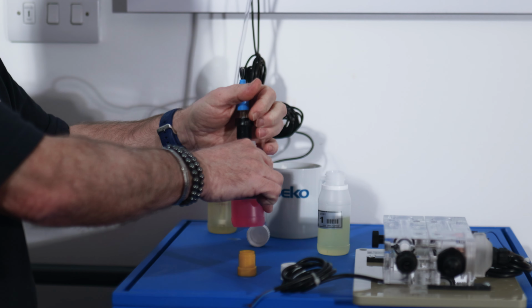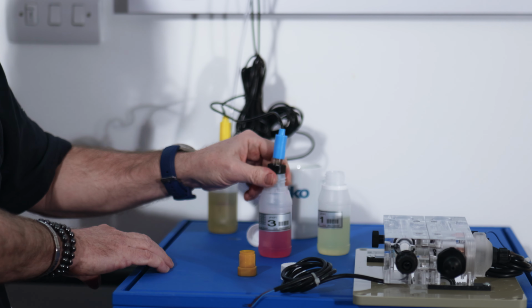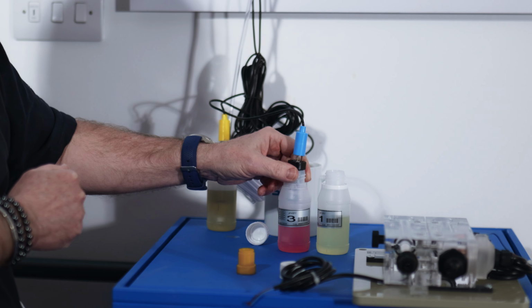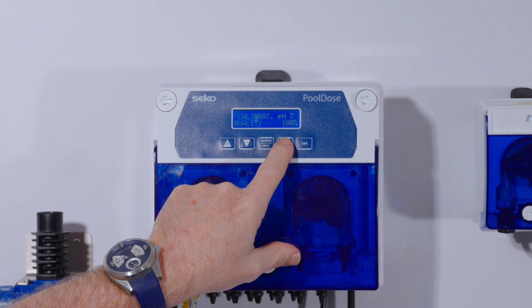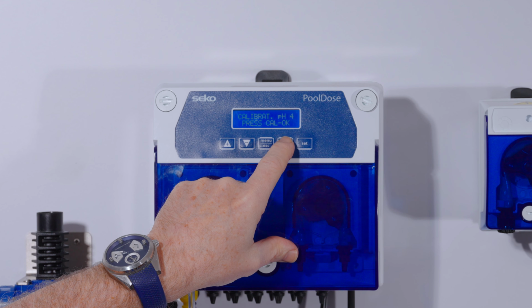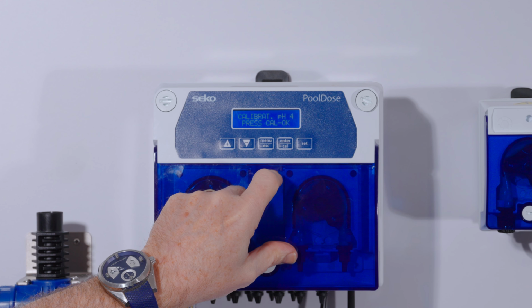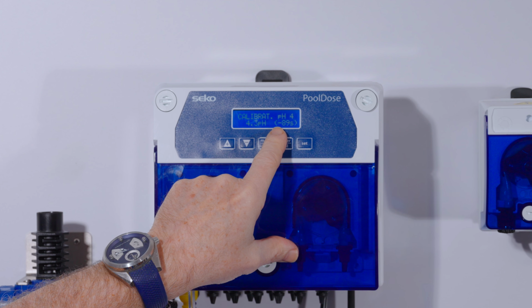I should say never rub the probes to dry them off or clean them because electrical interference will damage the probe. We then go back to the menu, press enter to continue with the calibration. You can see that's now changed to pH 4, and if we press enter, once again we'll begin the countdown process.